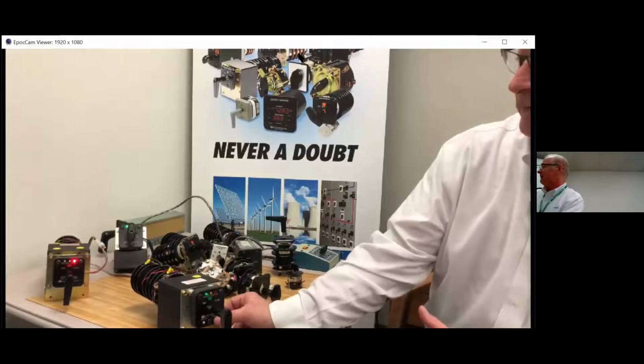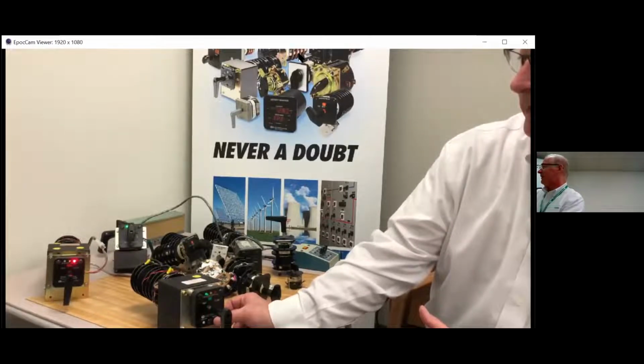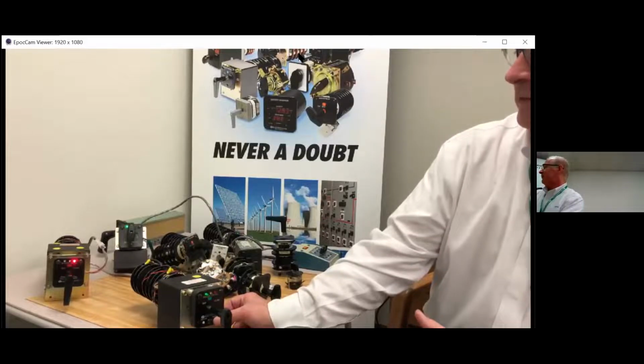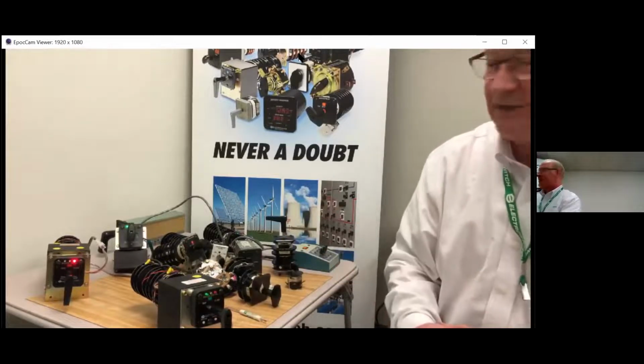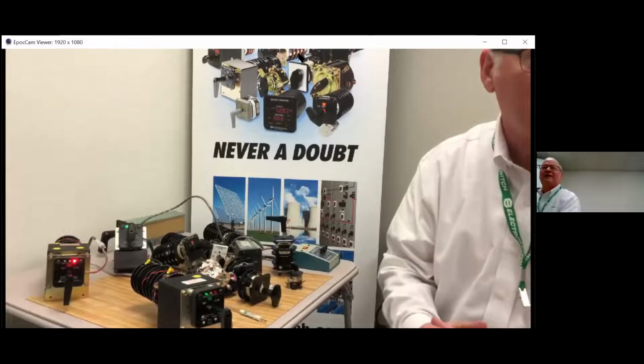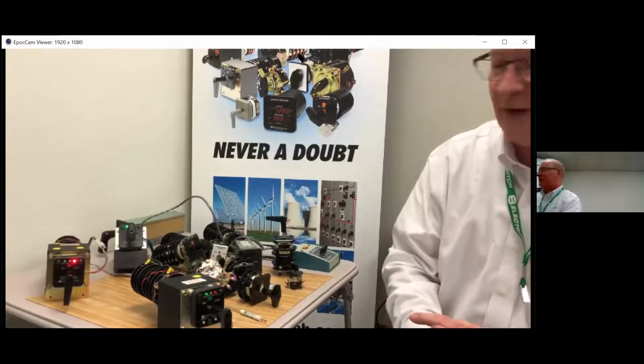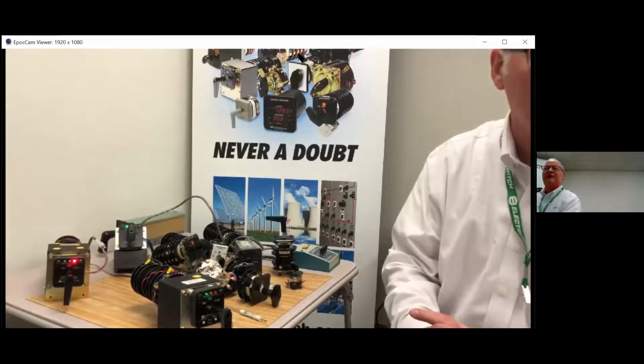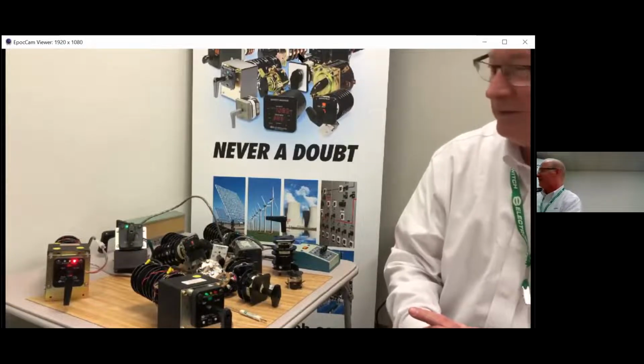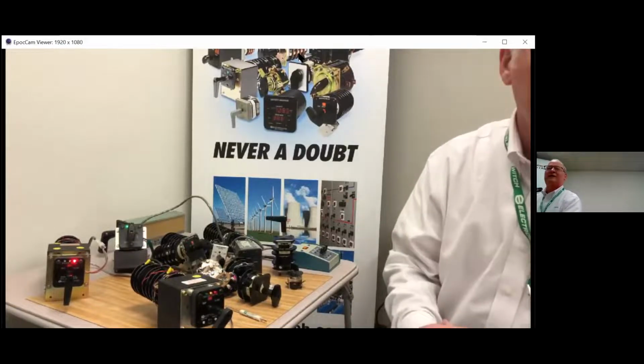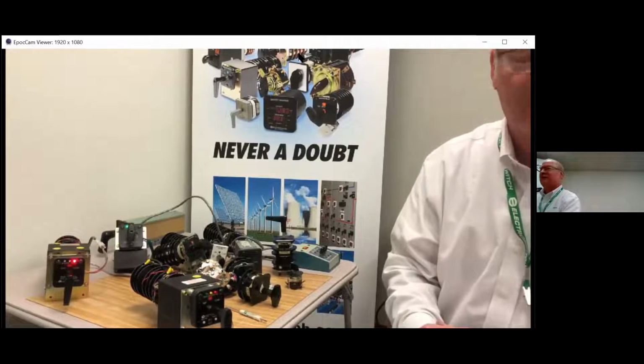And then go ahead and find the problem I needed to solve, and then go ahead and reactivate the button, hold it down for 4 seconds. The red LED will start timing for 10 seconds. I run like heck to get out of the room so I don't have to worry about closing into a breaker that potentially could hurt somebody, and it goes ahead and trips automatically.